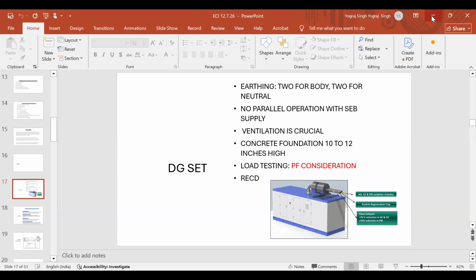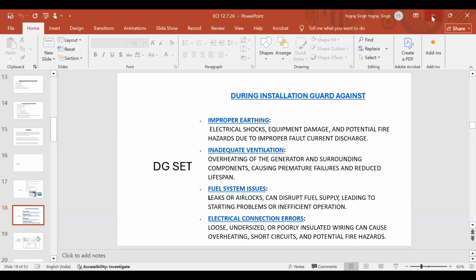Now, nowadays DG sets all come in an enclosure like this. But still ventilation is very crucial. If this enclosure is kept outside in the open, then ventilation is not very critical. But here there should be sufficient ventilation, exhaust fan, and other things. So these things are important. Then this DG set container should be kept on rigid concrete ground, about 10 to 12 inches high.